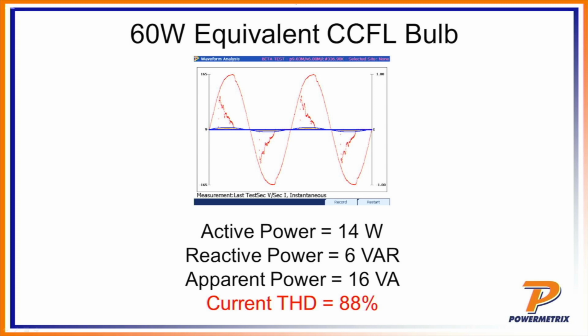I mentioned earlier about nonlinear loads not being sinusoidal. Once again, I've got a sinusoidal voltage going in, but now if we look at the current waveform, it looks like sort of a rugged mountain peak. And so this is just a surge of current being drawn on each and every half cycle of this waveform. The more jagged, the more sharp that peak is, the more harmonic energy is going to be consumed from that.